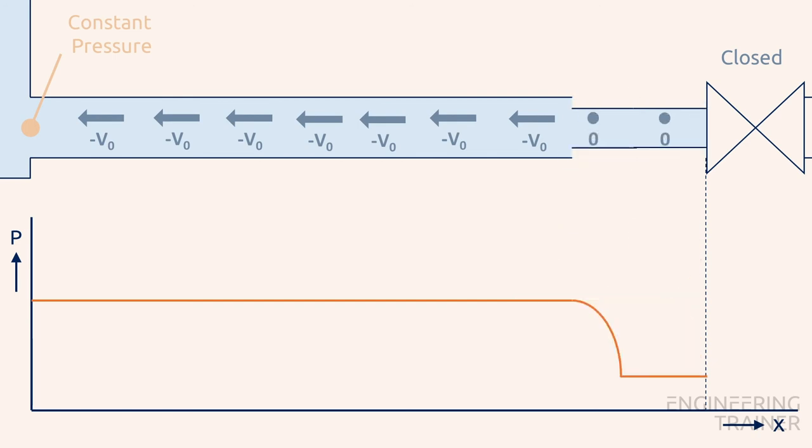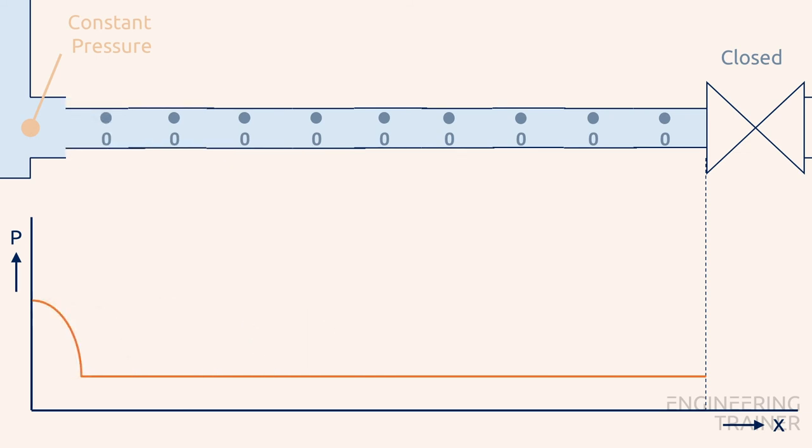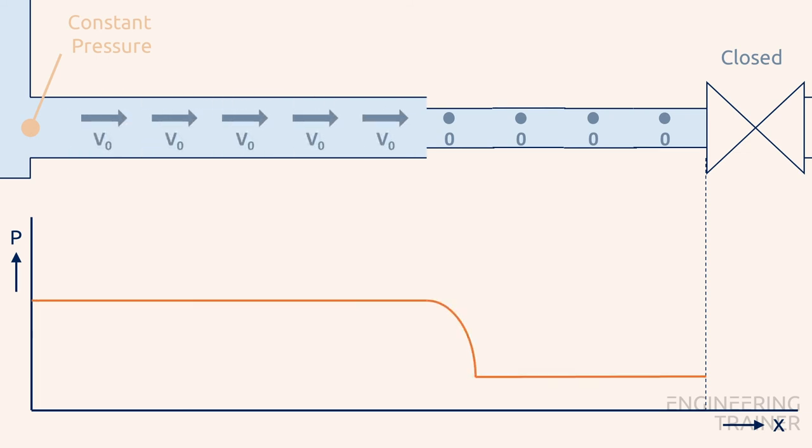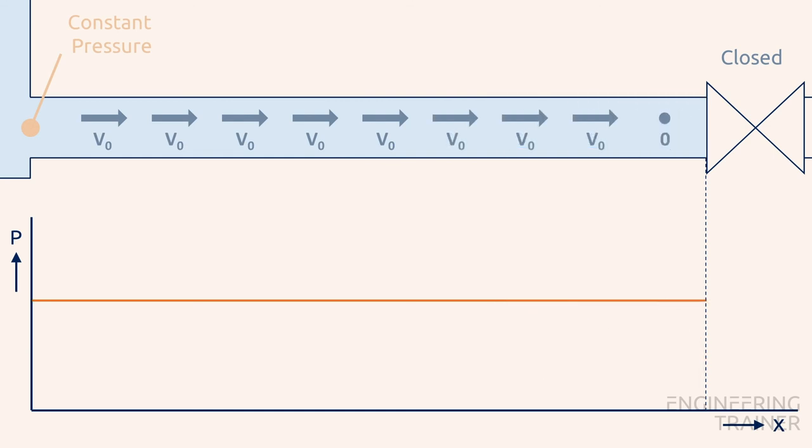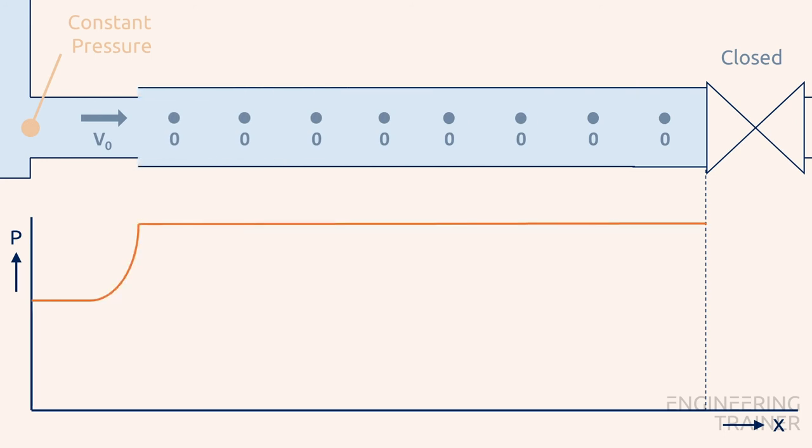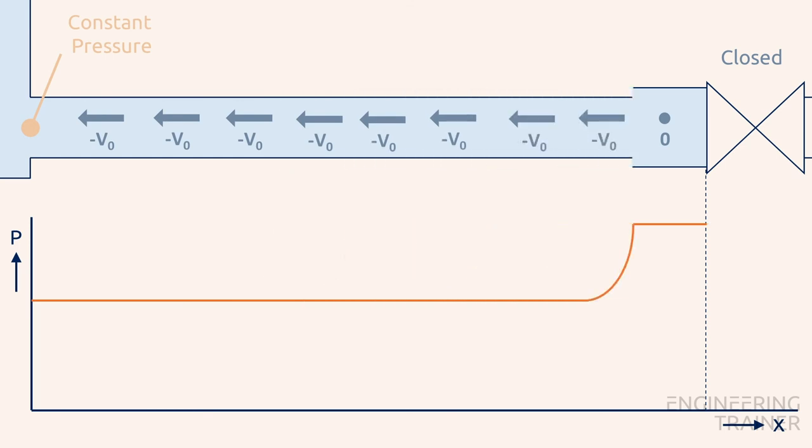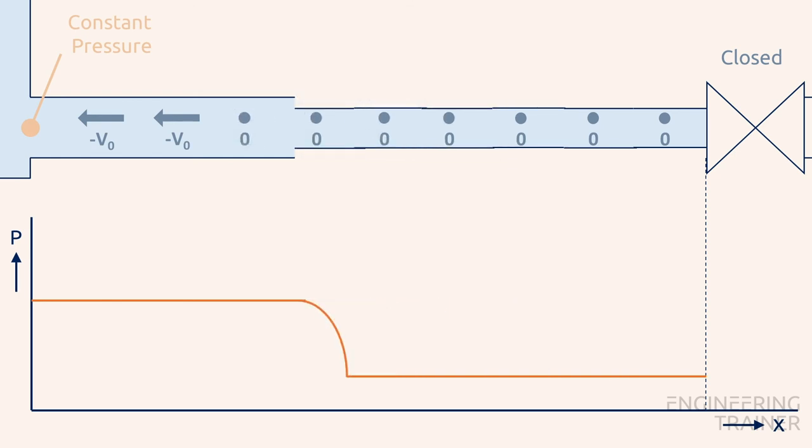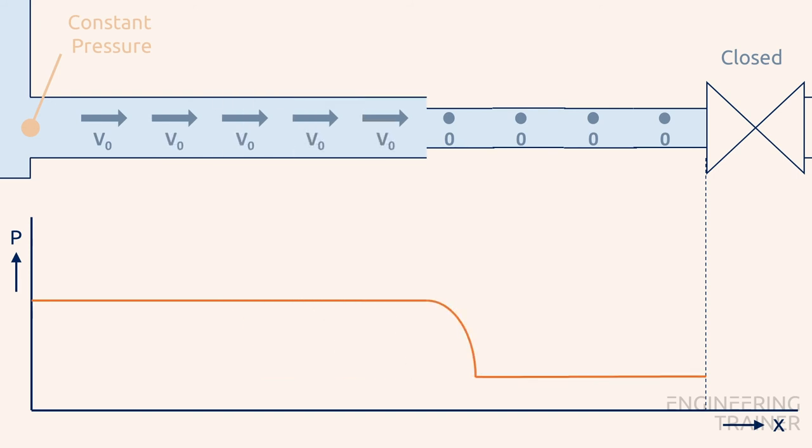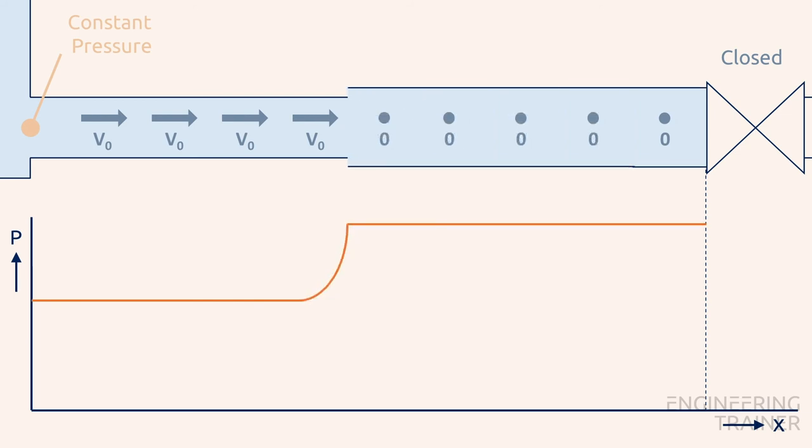Causes an expansion wave to start at the valve, which also reflects back to zero at the reservoir. In terms of flow we see that the flow is stopped starting at the valve, then flows back into the reservoir, then is stopped again starting at the valve, and then starts running from the reservoir into the pipe again. As long as we neglect the friction this loop of pressure waves will keep going indefinitely.